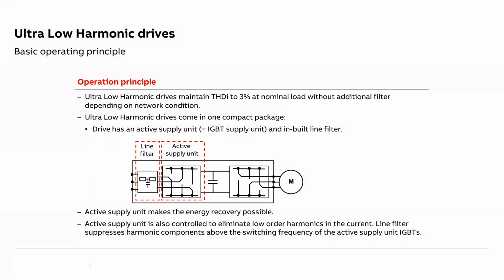Active front end technology, this basically is a drive. It consists of a basic drive. However, on the input side, instead of a rectifier bridge, it has an IGBT bridge, plus a line filter. So this restricts the harmonics. This controls the harmonics, and we can bring it down to levels of 3%. So we can say that it combines a standard VFD plus an active filter together.